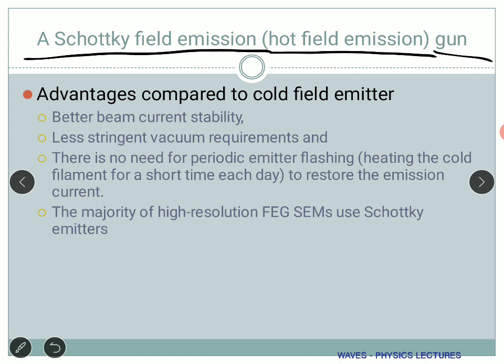The Schottky gun is a combined effect of temperature and field. Its advantages are better beam current stability and less stringent vacuum requirements. In a scanning electron microscope you need a good vacuum to avoid unwanted processes — if there is air, the high-energy electrons might cause ionization. But with the heated filament combined with the field, less vacuum is required.